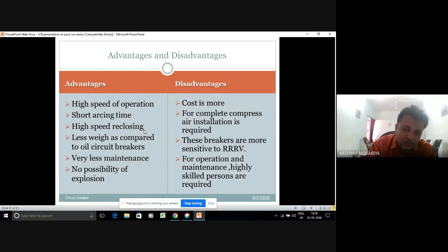So in this presentation, the design and ratings of the reclosers are also covered. Operation and maintenance require highly skilled persons, because you have to deal with a number of things. You have to deal with the compressed air, the reservoir, the resistance switching unit, and the moving assemblies. But through my experience, I can tell you that once you have good hands-on experience one or two times on any type of breaker, then obviously in future you can work with it very comfortably. So this is the advantage and disadvantage.